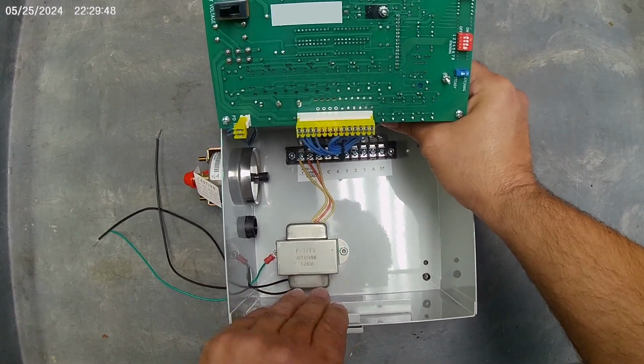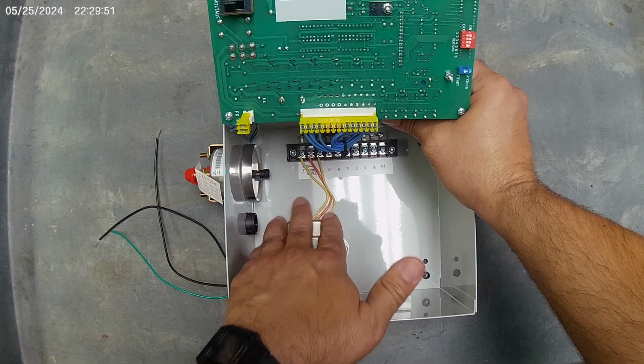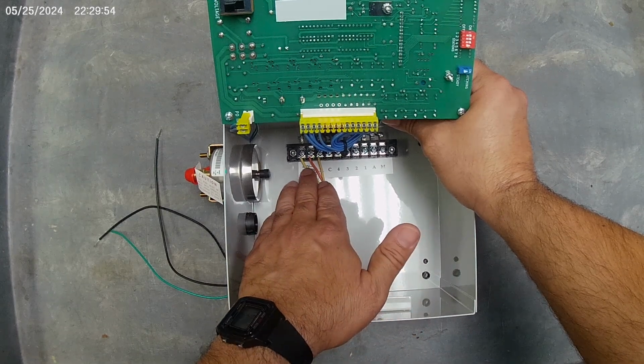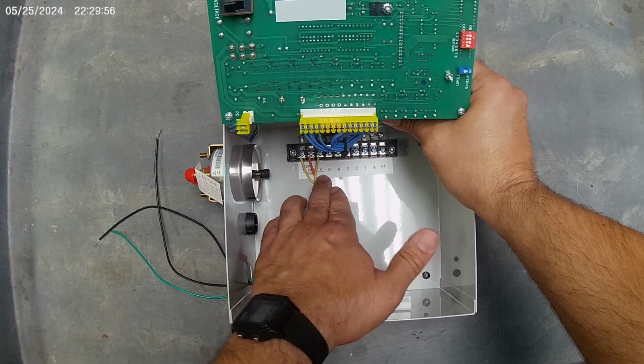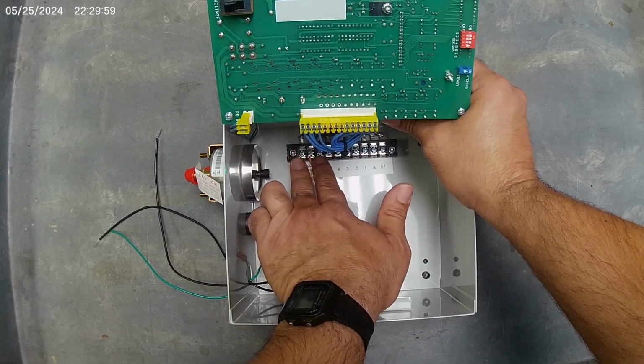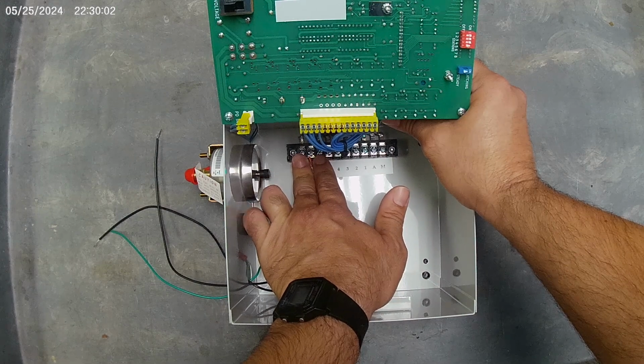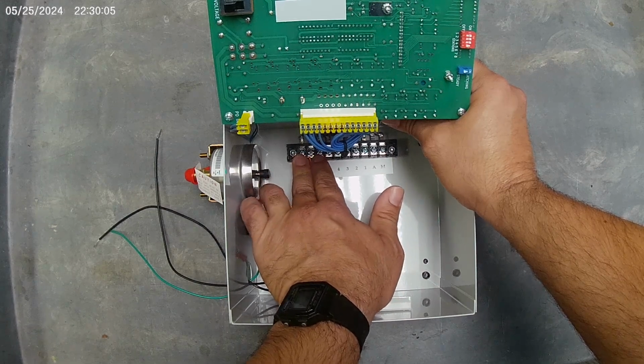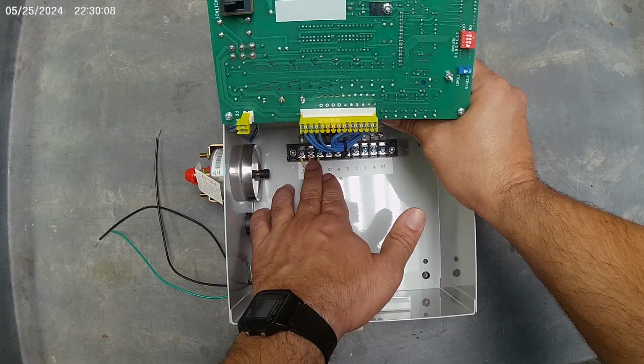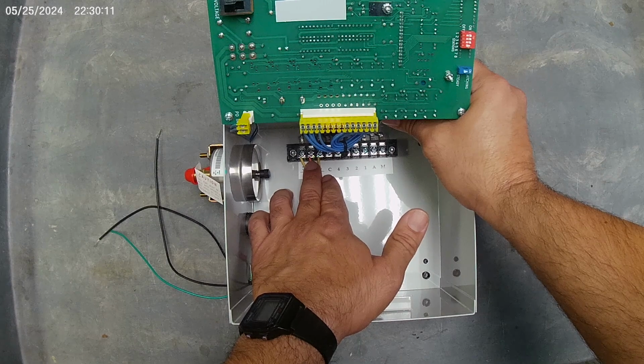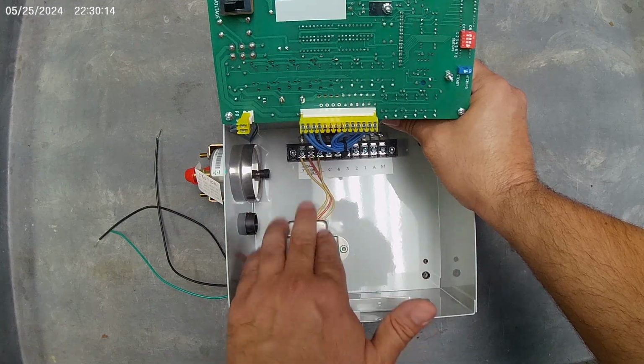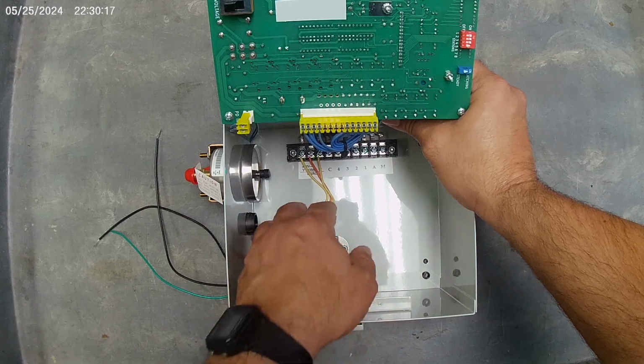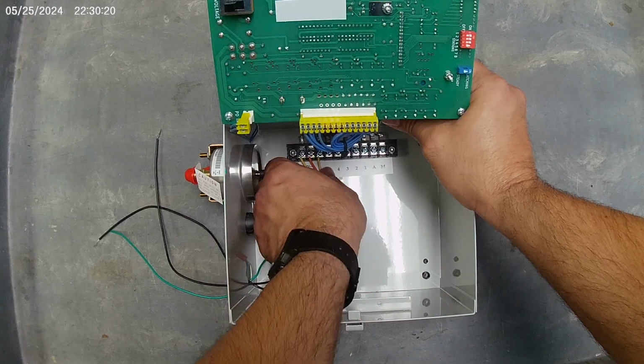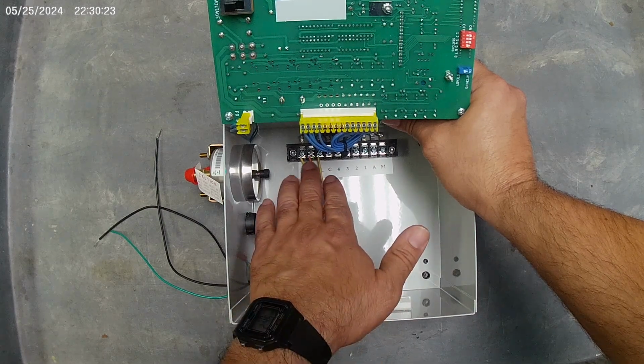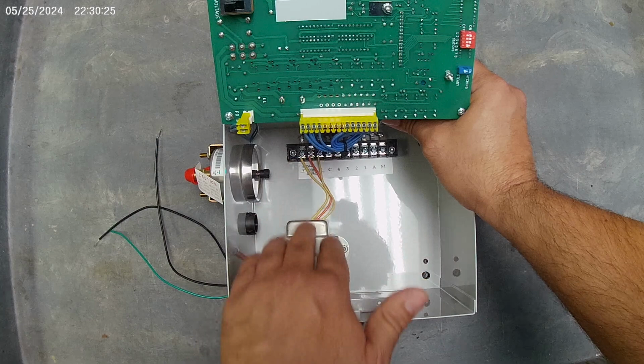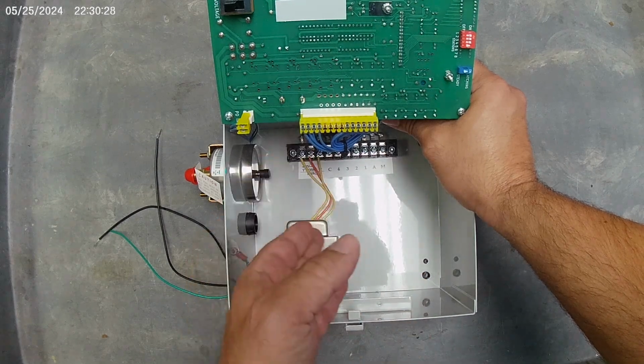The transformers used in these controllers is a 24-volt center tap transformer. The standard transformer uses yellow, orange, and yellow wires. To test this, you would measure across the 2 yellows and you would get nominally 24 volts. It's typically a little higher, 26 or even up to 28 volts maximum, with half as much between the yellow and the orange wire. If you're not getting that, then something's wrong. We suspect your transformer of being bad. If you're using a battery or solar setup, we recommend removing the transformer altogether, because if a battery is wired in parallel with this transformer, it would be a dead short and just simply burn up everything here.